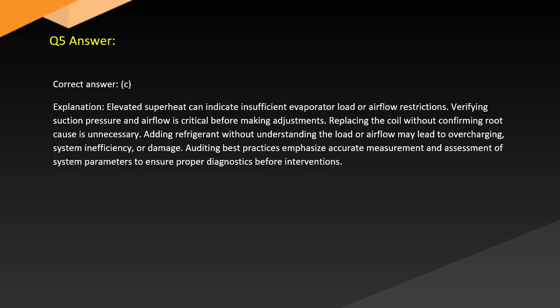Answer. Correct answer: C. Explanation. Elevated superheat can indicate insufficient evaporator load or airflow restrictions. Verifying suction pressure and airflow is critical before making adjustments. Replacing the coil without confirming root cause is unnecessary. Adding refrigerant without understanding the load or airflow may lead to overcharging, system inefficiency, or damage. Auditing best practices emphasize accurate measurement and assessment of system parameters to ensure proper diagnostics before interventions.